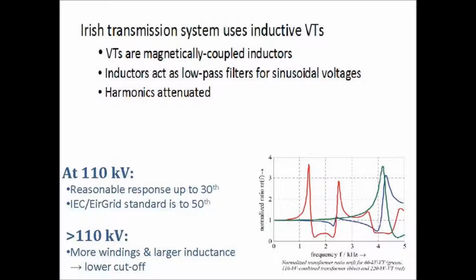And then for 220 kV, the red plot, obviously that shoots off very low down, so it's very, very hard to make any kind of harmonic measurements at 220 kV and beyond. So at 110 kV, we're happy enough with them up as far as the 30th harmonic. From 30 to 50, which is where the standard ends, measurements are a little bit more difficult to come by, and you need higher grade equipment to be able to work that out. And beyond 110, it's very difficult to do so due to the larger impedances.